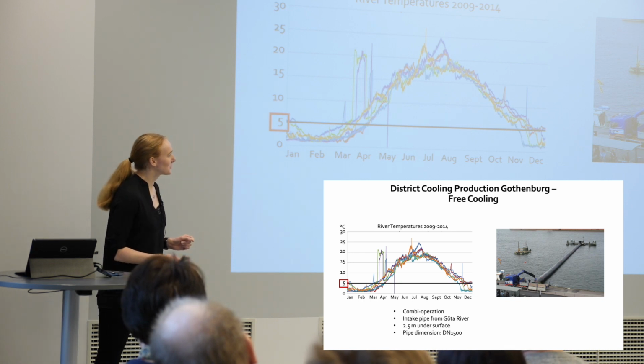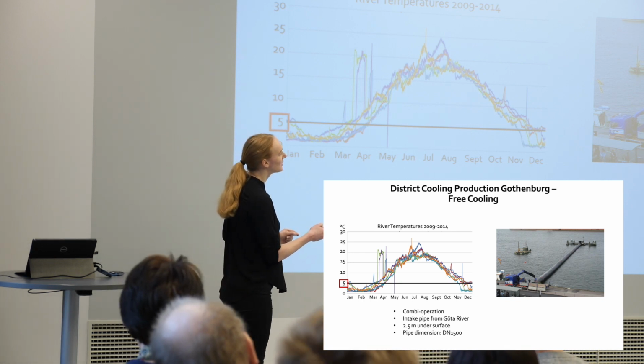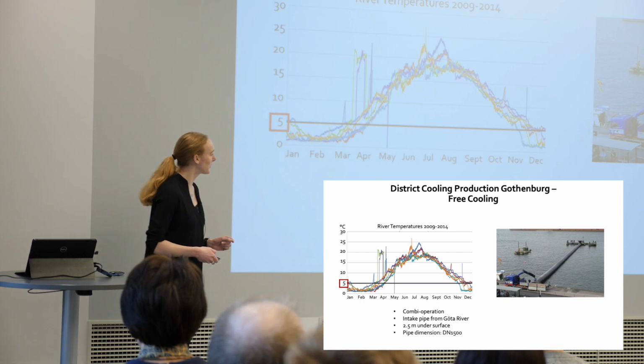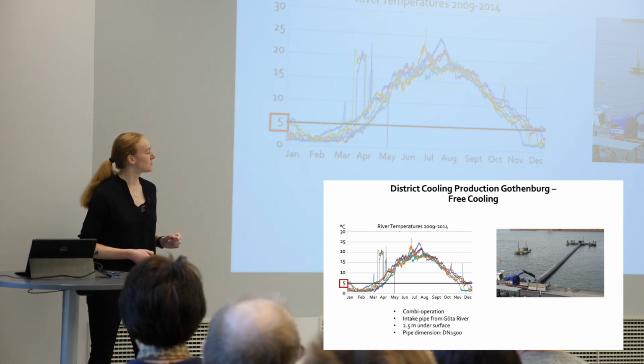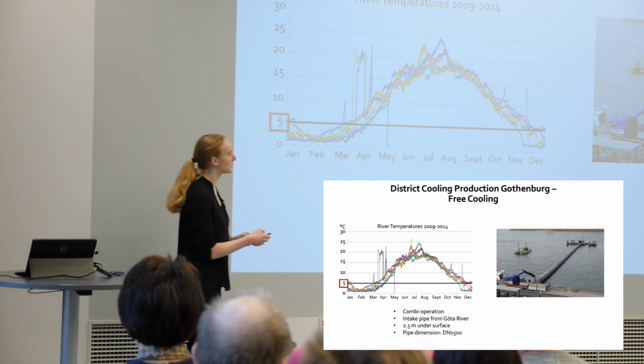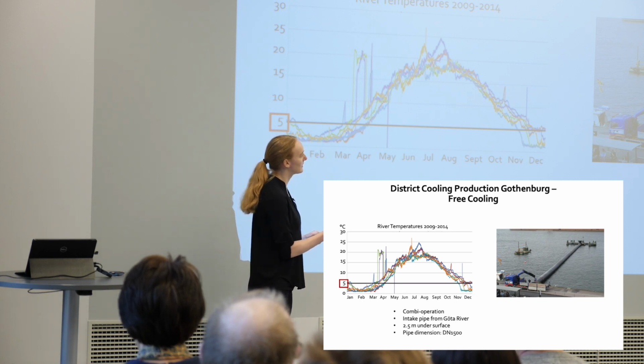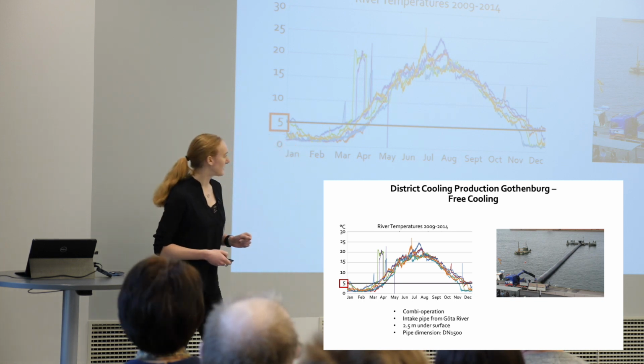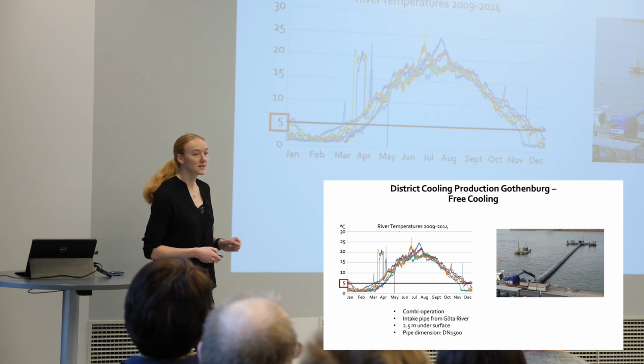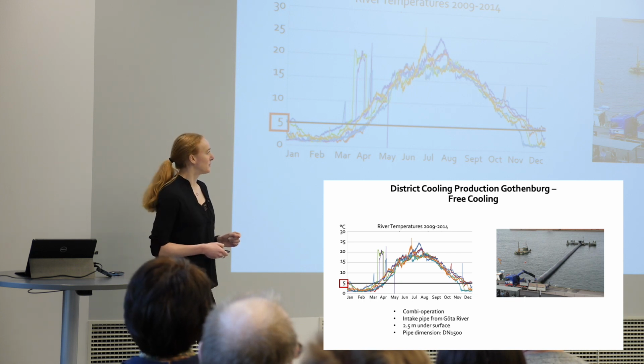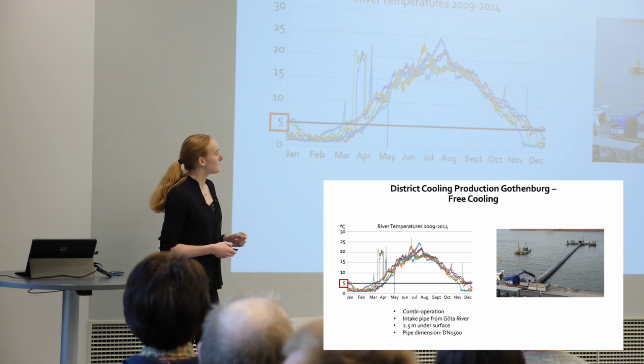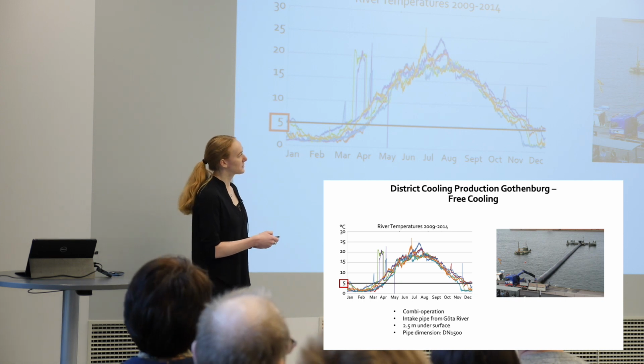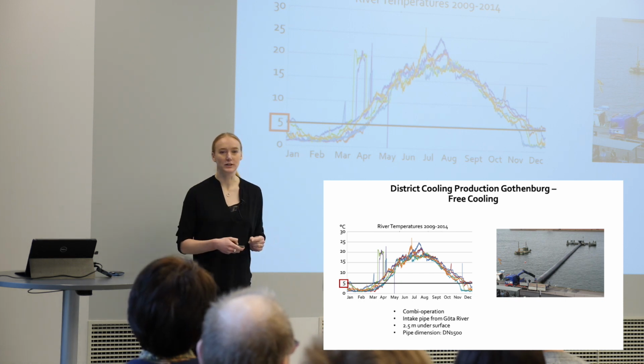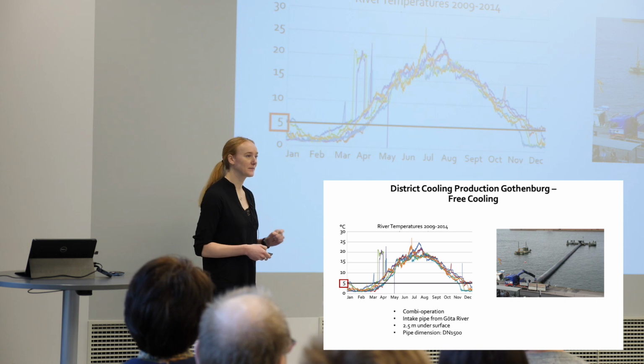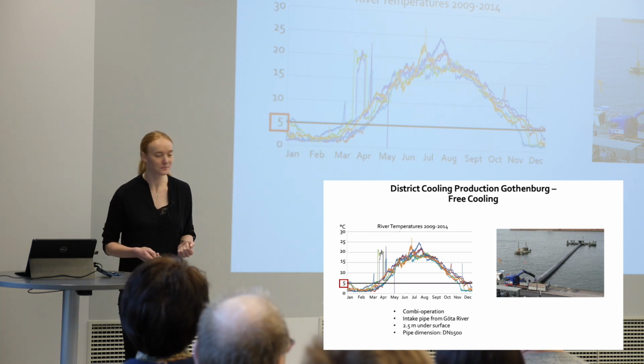And here you can also see the intake of the free cooling. It's out in the river. This pipe is 2.5 meters below the surface. This is when they're putting it in. And the pipe dimension is 1.5 meters. And it goes into the production facility where the chillers, absorption, and the biggest production facility that we have.